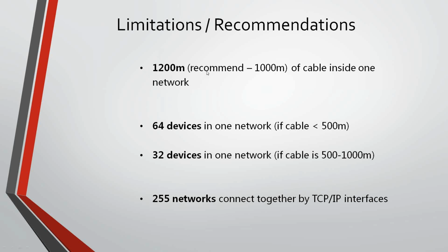1,200 meters of cable, but we recommend 1,000 meters of cable inside one network. 64 devices can be connected together in one network if you use less than 500 meters of cable, 32 devices if you use from 500 to 1,000 meters. That's it, these are the limitations.